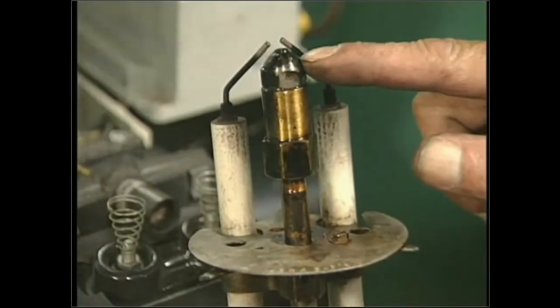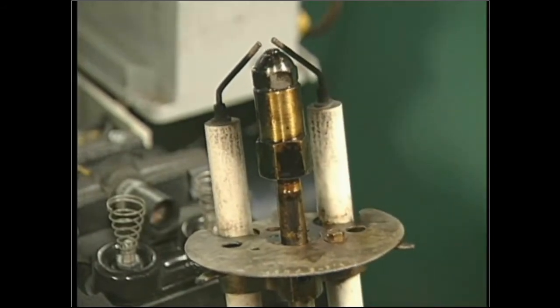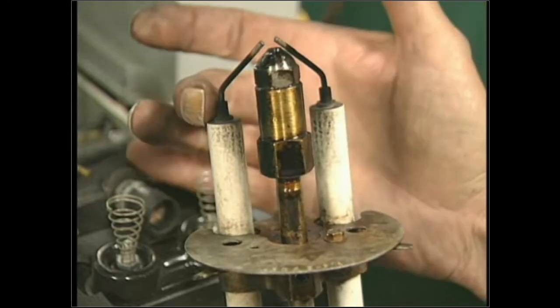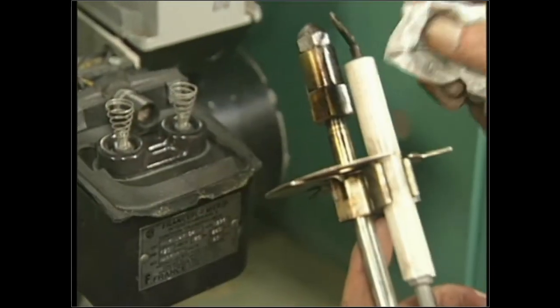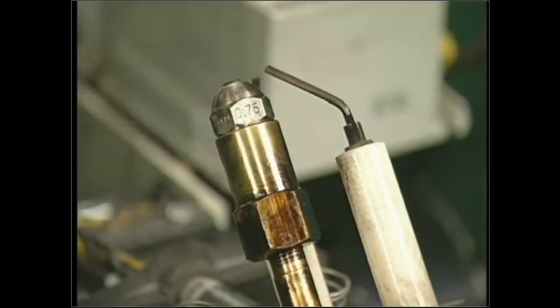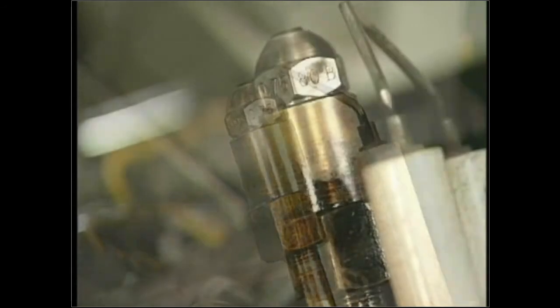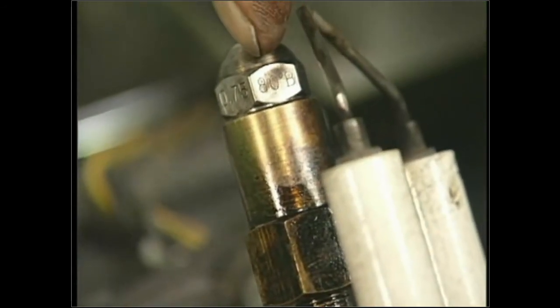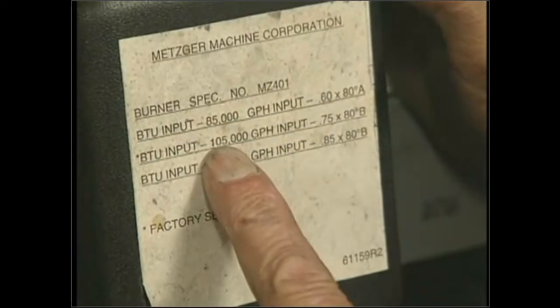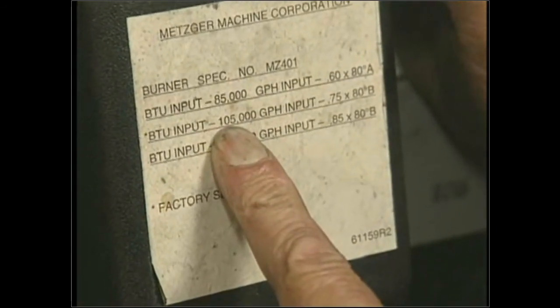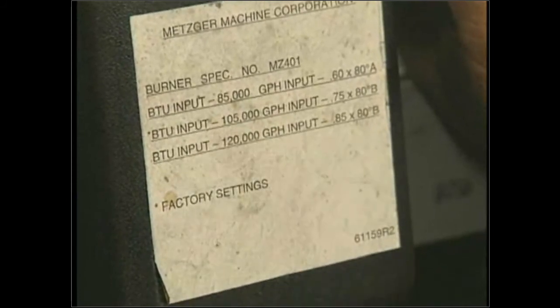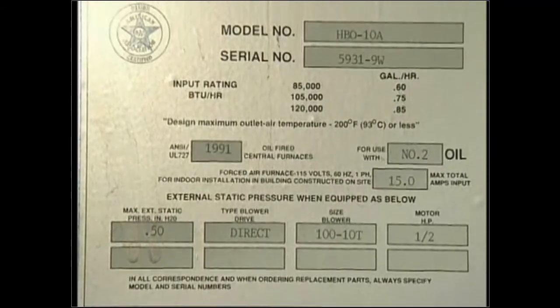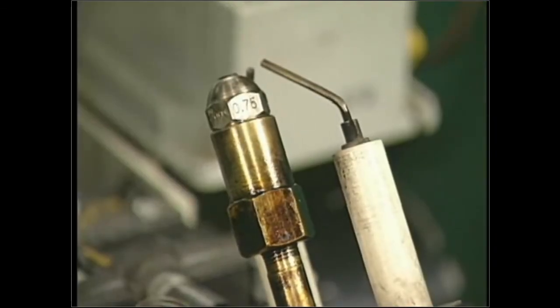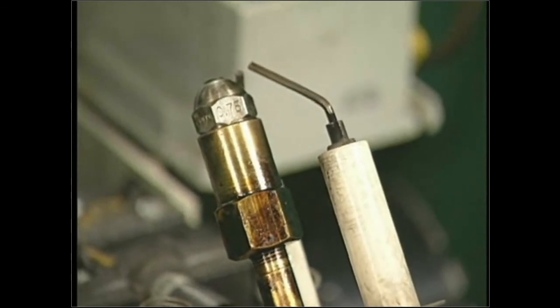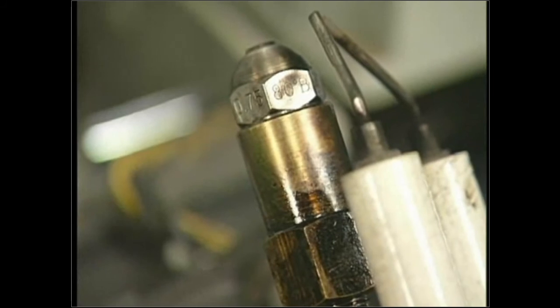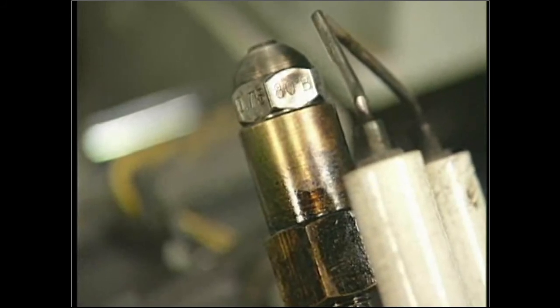The burner consists of a nozzle, a burner assembly, an electrode on one side of the nozzle and an electrode on the other side of the nozzle. The nozzle should be cleaned well enough with a cloth or paper towel so the nozzle size can be revealed and documented. With a slight turn of the burner assembly, the nozzle will also display the spray pattern measurement, which should also be documented. Upon recording the size and spray pattern stamped on the nozzle, it should then be checked with the manufacturer's specifications on the furnace to match the BTU needs of the home. Improper nozzle sizing can once again lead to overfiring, inefficiency, and premature wear on the system. Proper nozzle sizing can optimize safety, comfort, and efficiency.